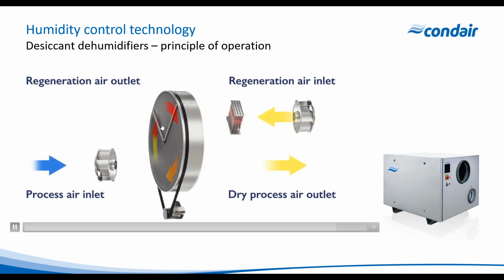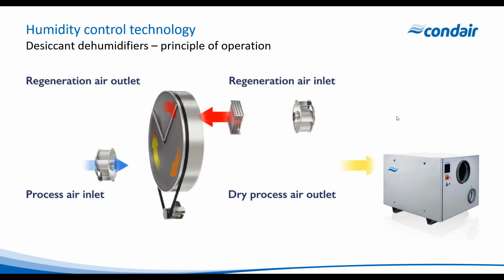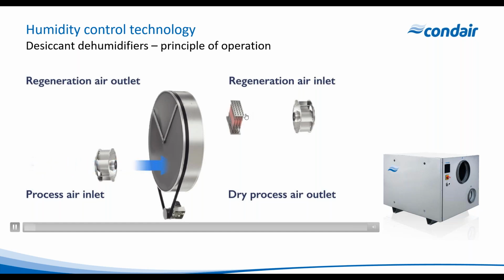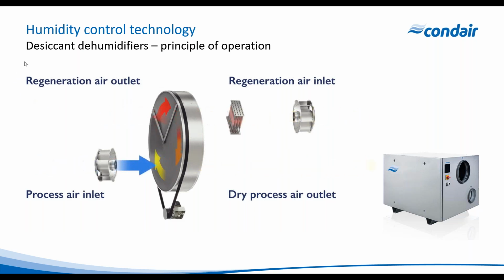But then you've got a problem, because you've got a desiccant wheel that's full of moisture. So how this is controlled is that we take an air supply from outside the room that goes through a fan over a heater, where we heat the air up to maybe 120 degrees C, and we dry a section of that rotor. We then take that wet air and duct it out to ambient to release the water back into the ambient. So these systems are great for larger duties or lower relative humidities because we're not limited by a refrigeration cycle here. We can go down to dew points of minus 30, minus 40 for specialist applications. But for a heritage application, it tends to be a larger application with larger air volumes and a central air handling unit.